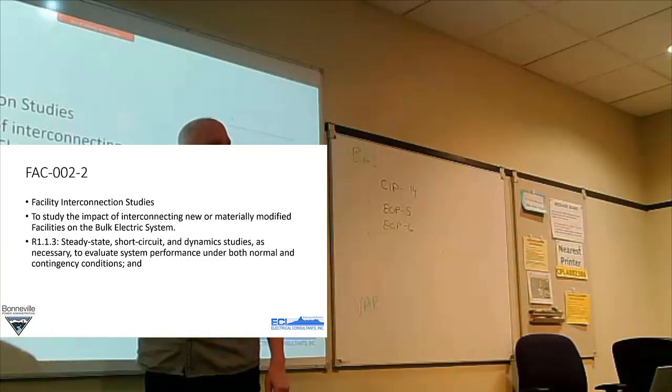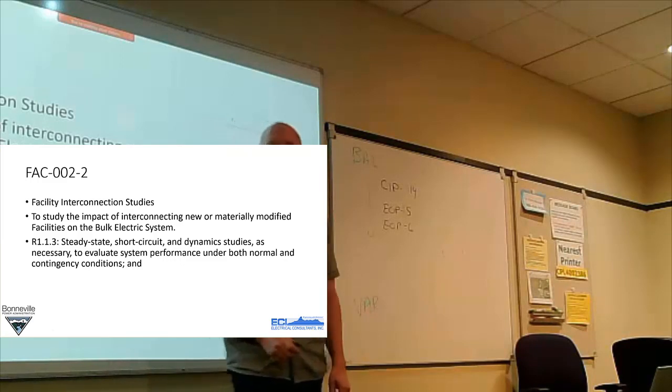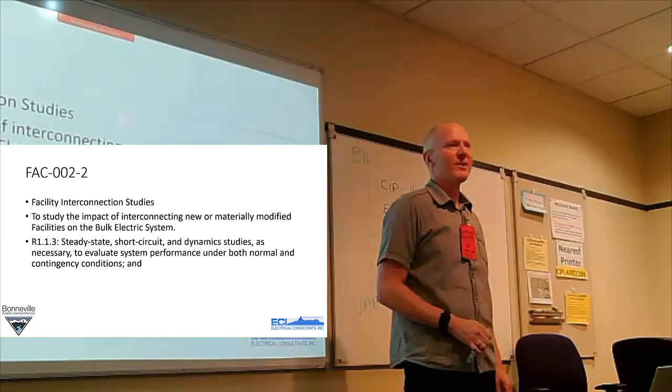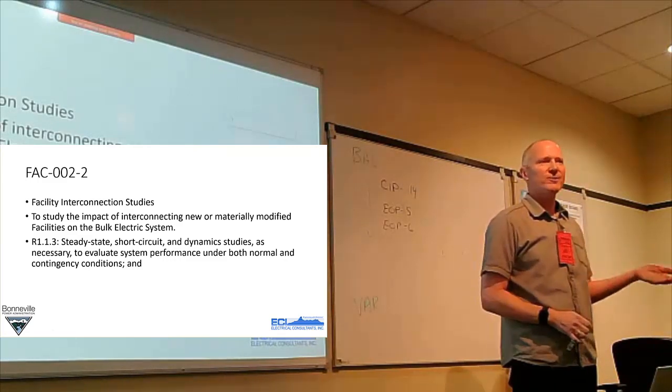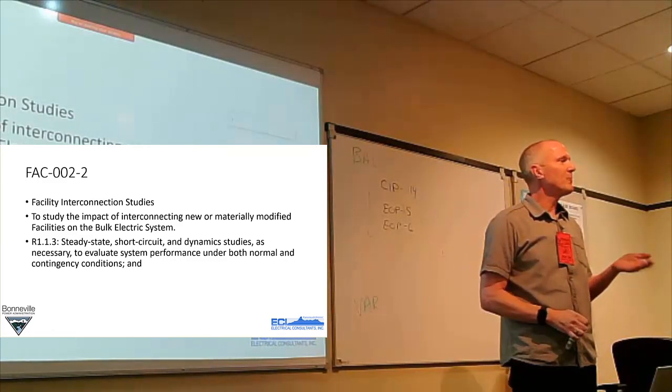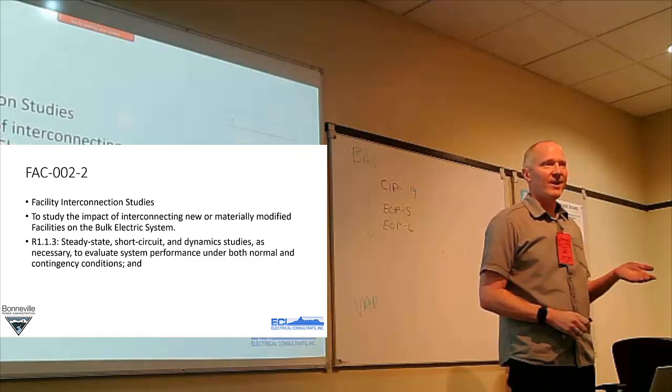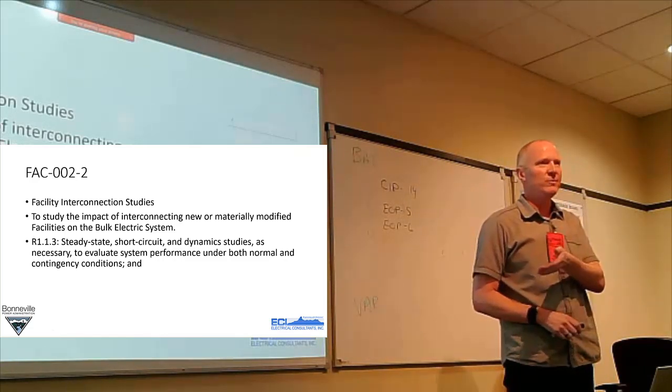I've seen people do pretty big projects with a steady state analysis, and that's it. And I think you're leaving your planner open to pain and suffering when they run the annual assessment with all of its transient stability and short circuit stuff and find out, oh my gosh, what did we do? We didn't study this thing. And a FAC-002 could have saved you from doing that.